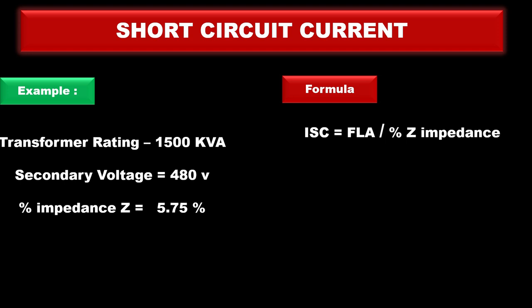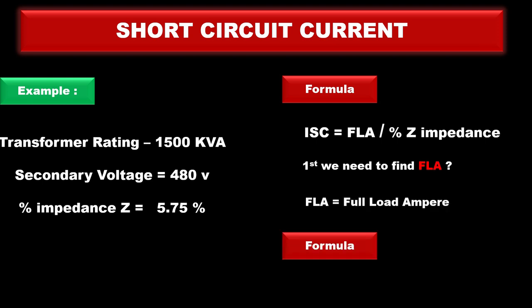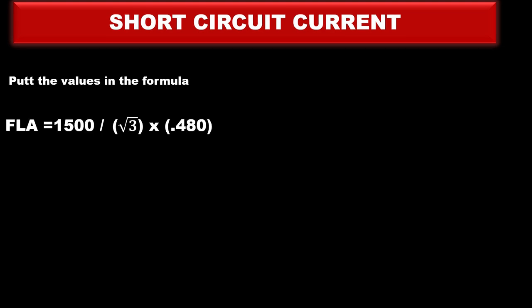First we find full load ampere. The formula for full load ampere is kVA divided by square root of 3 multiplied by voltage. So put the values in this formula: 1500 kVA divided by square root 3 multiplied by voltage. Voltage is 0.480, so the answer is full load ampere equals 1804 amperes.